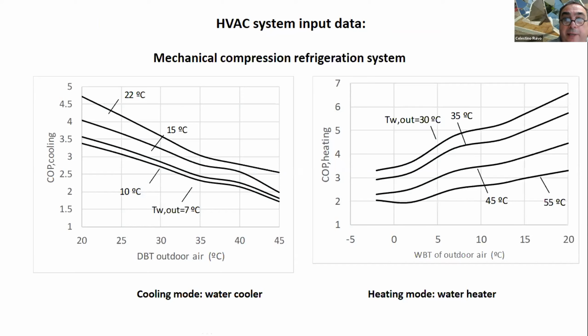Regarding the mechanical compression refrigeration system, it can operate in cooling mode as a water cooler and in heating mode as a water heater. And here you can observe how the COP in each mode is influenced by the outdoor conditions, by the dry bulb temperature in cooling mode, and by the water temperature that is being produced. And here the same information regarding the heating mode. These data were obtained from the technical catalog of the manufacturer, and these data were implemented in TRNSYS and considered in the simulation.